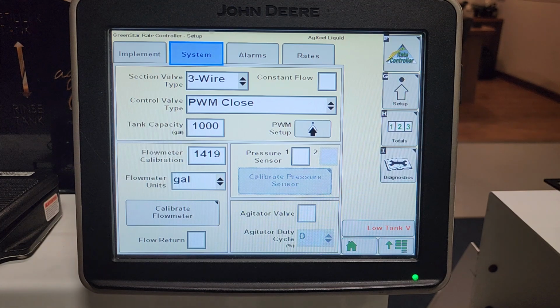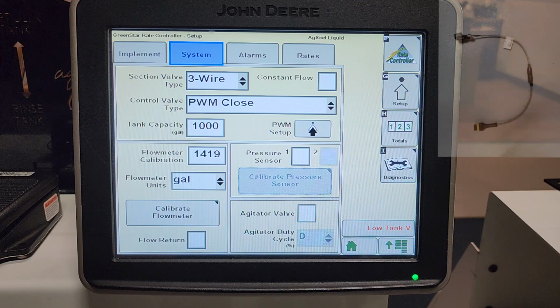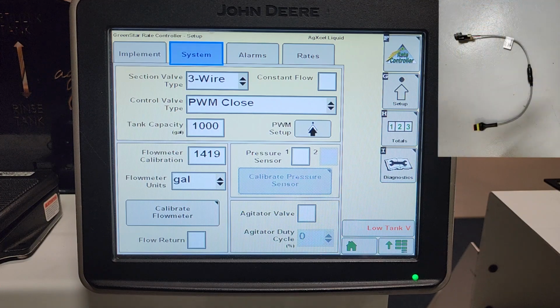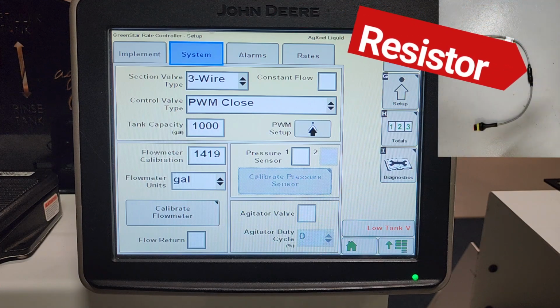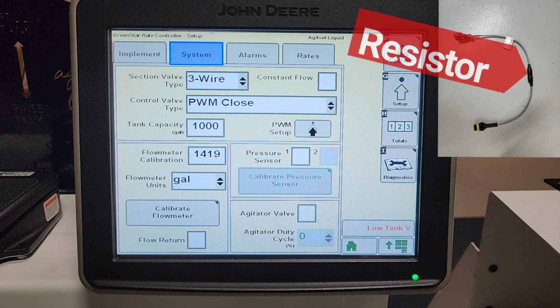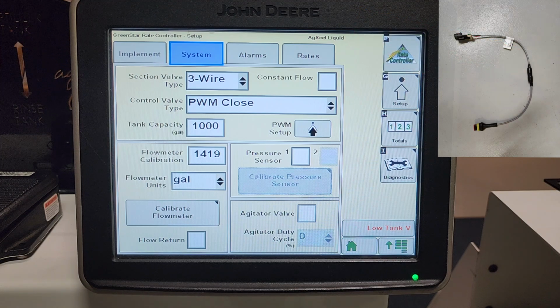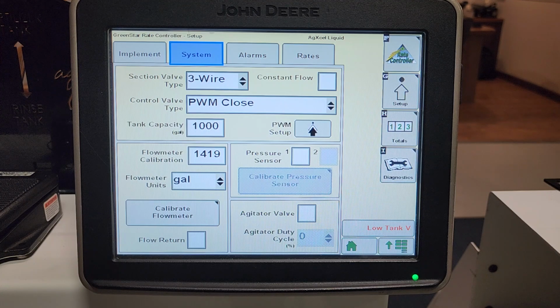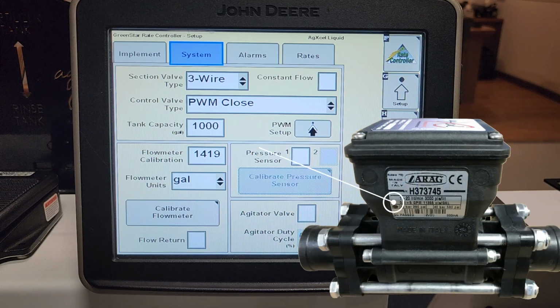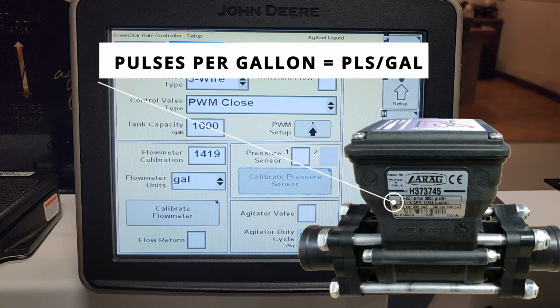So because of that, this foot-long adapter cable you'll have to use in place, and that black shrink-wrapped piece in the middle is a resistor. What that does, it divides your pulses by 8, so we just call the cable a divide by 8 cable. So what you'll have to do is, when you look on the side of the flow meter, you'll see here where it says pulses per gallon.